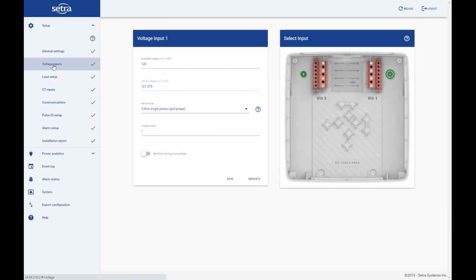If I go to voltage inputs, you can see the halo dot that I mentioned in the presentation and the 2 voltage inputs. As I switch those, you can see the halo switch and the setup change. And you can see the actual voltage reading right there on the voltage setup. We do allow for potential transformers, so you can put in a voltage scaler for that transformer to make sure your power and energy data is correct based on what's before the potential transformer.